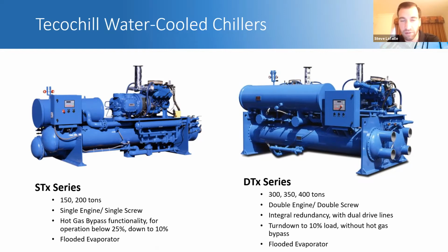If you look at our part load curve, our efficiency is going up essentially almost the whole way down in load, which is the case for most VFD screw machines. And it is an industrial screw compressor, as you can probably see there. Normally there's an acoustic enclosure over the engine and compressor, but it's kind of removed for clarity. But that's an industrial screw compressor like you would see in an industrial refrigeration plant. So very robust. We do a lot of process cooling with this machine.